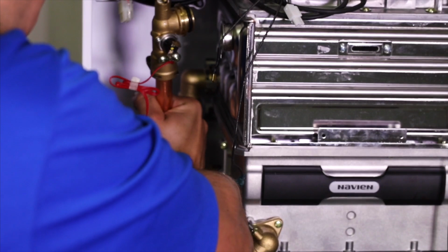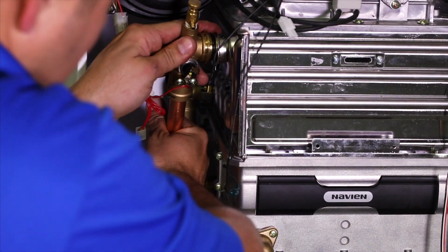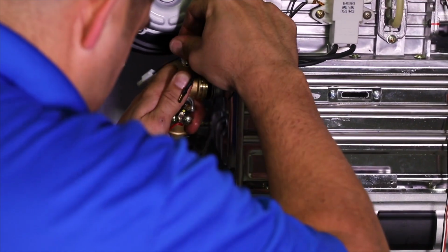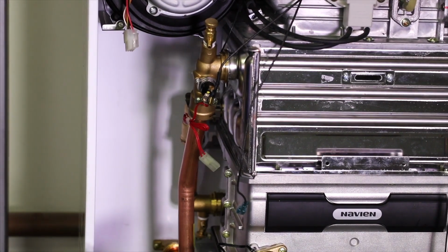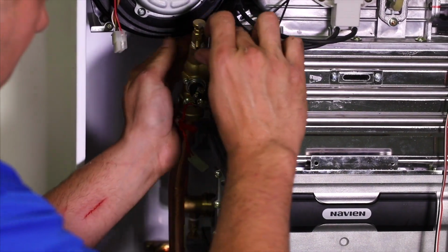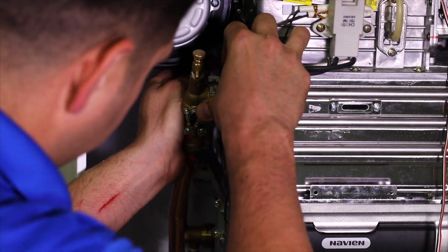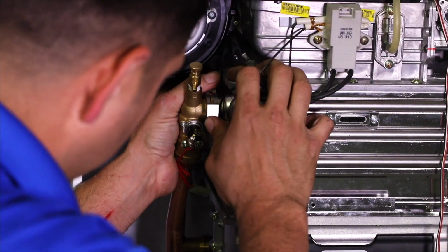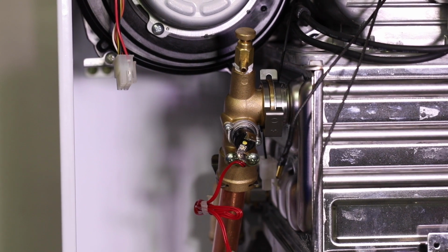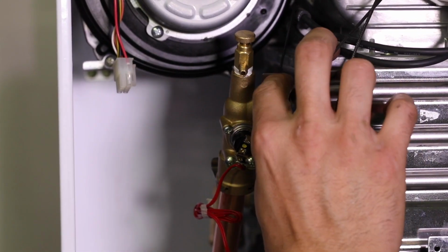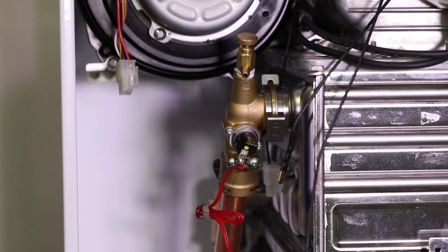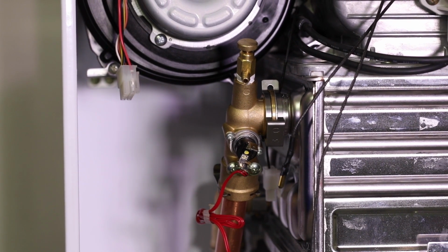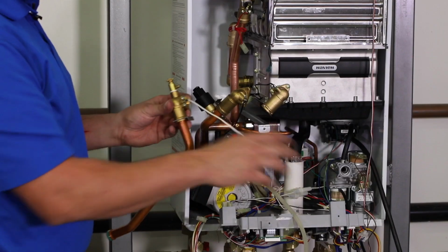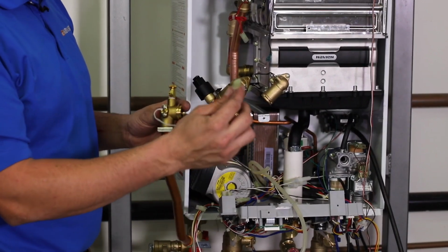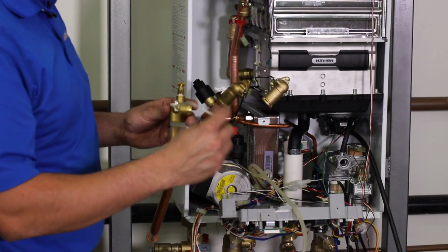Another thing to be very aware of is as you're installing this elbow on the outlet of the primary heat exchanger, this clip goes over these two flanges. You got to make sure that both your elbow and your heat exchanger, the flange on there, are completely seated properly and flat, flush against each other. Pop that clip over it and it should lock in those two flanges so they can't pop apart. Our old temperature sensor had a white lead. Our new one has a red lead or red wire coming out of it.